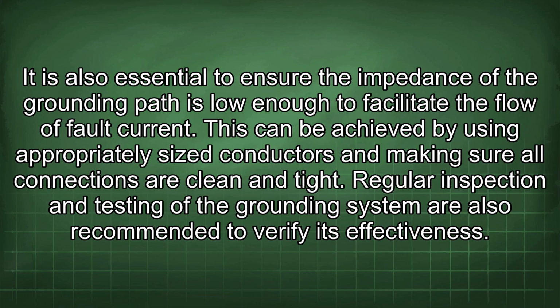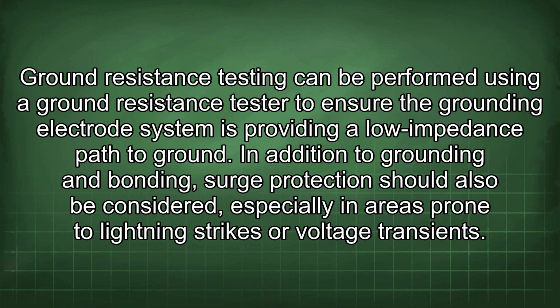Regular inspection and testing of the grounding system are also recommended to verify its effectiveness. Ground resistance testing can be performed using a ground resistance tester to ensure the grounding electrode system is providing a low impedance path to ground.